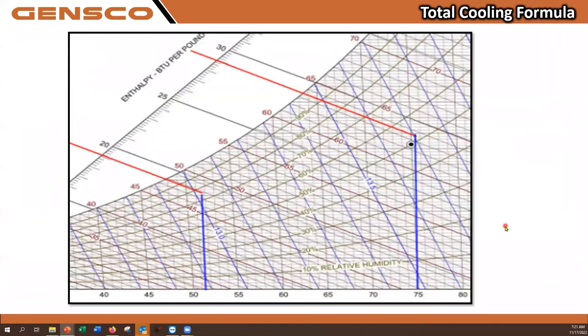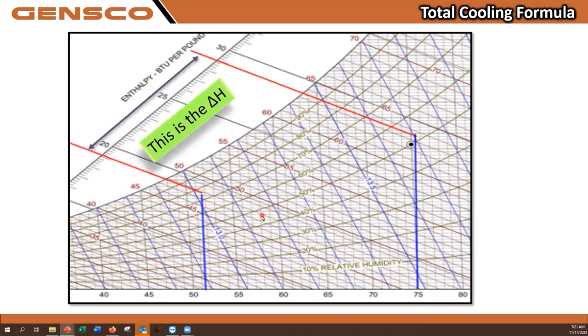This would be an example of actually plotting the temperatures that we just measured on a psychrometric chart. 75 degree dry bulb, 51 degree exit air, and our humidity points, 54%, 78%. And when we intersect the vertical dry bulb temperature line with the horizontal BTU line, here is my BTUs per pound, and the difference between my two red lines here on the chart, this is my delta H.